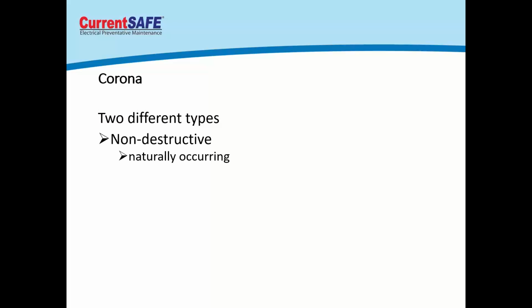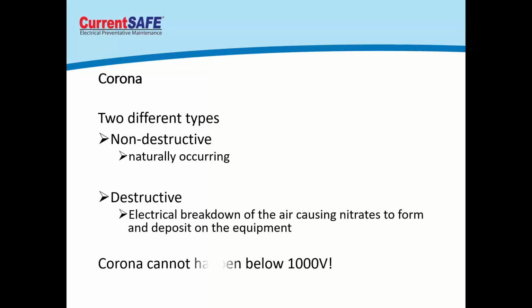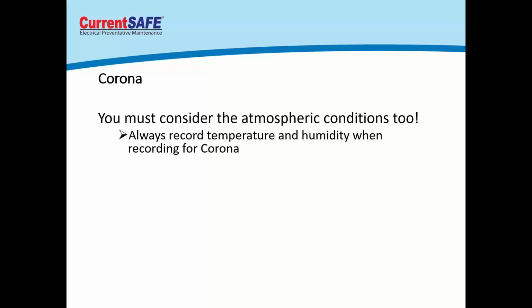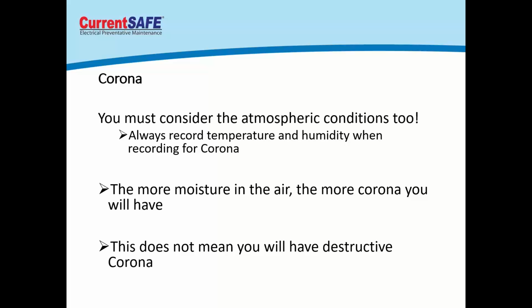Corona is a naturally occurring thing when you have medium voltage systems. So you can have destructive and non-destructive types of corona. Destructive means that we are actually breaking down the insulation parts and pieces, building up nitrates on things, and nitrates, when they get wet, make nitric acid, and then the acid starts eating the components. So corona can be a very bad thing when you're in the medium voltage as well.